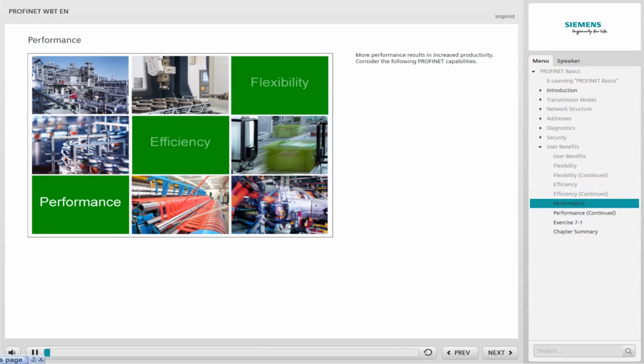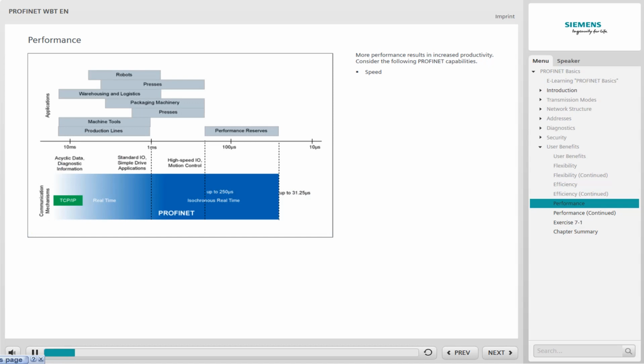More performance results in increased productivity. Consider the following PROFINET capabilities. With very short cycle times, PROFINET allows maximum productivity of machines and plants. Short cycle times, independent of the network load, permit the implementation of high-performance applications. The scalable performance makes it possible to configure PROFINET stations individually depending on the requirement. The bandwidth and available controller performance is thus optimally utilized.